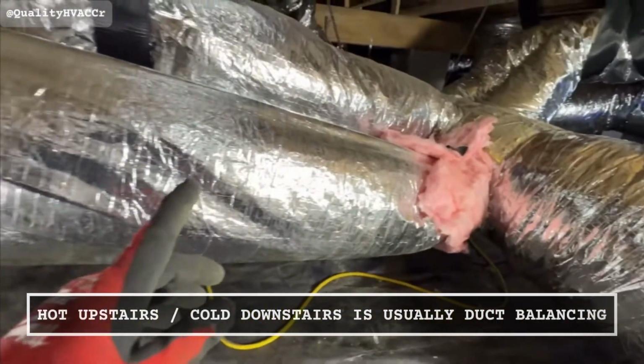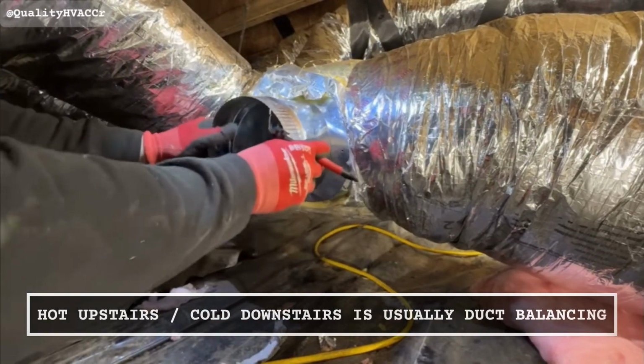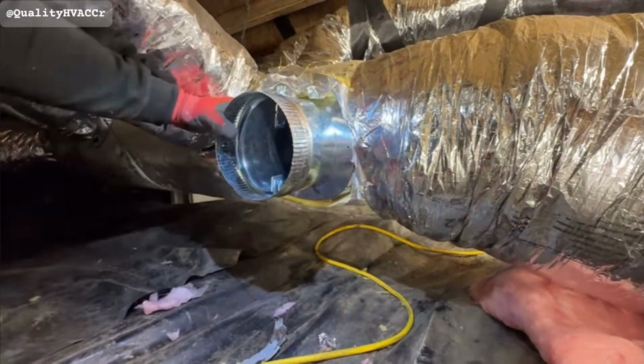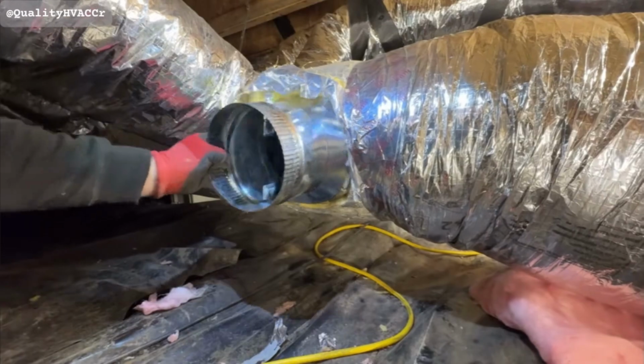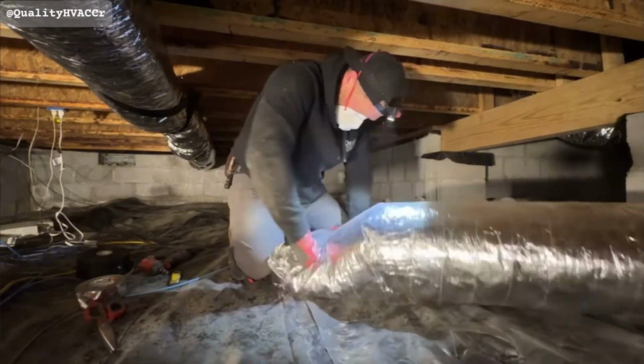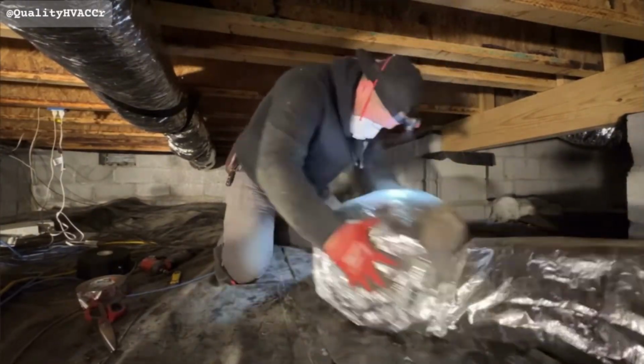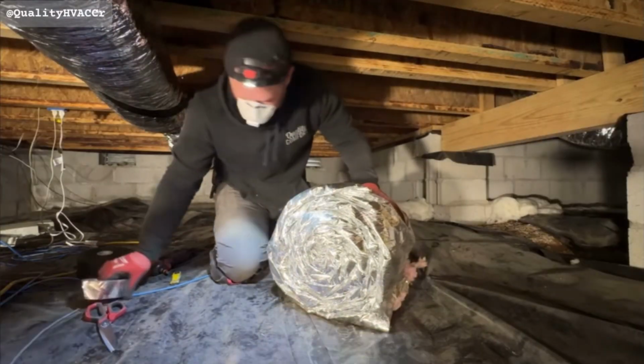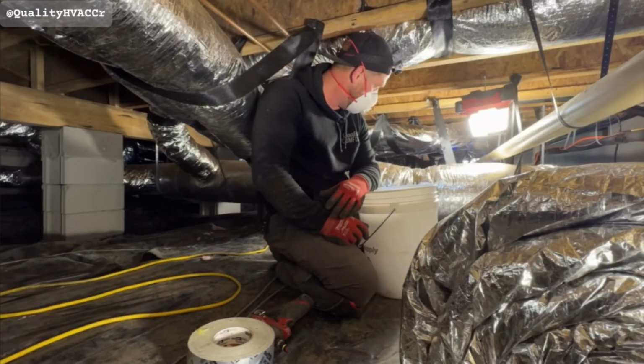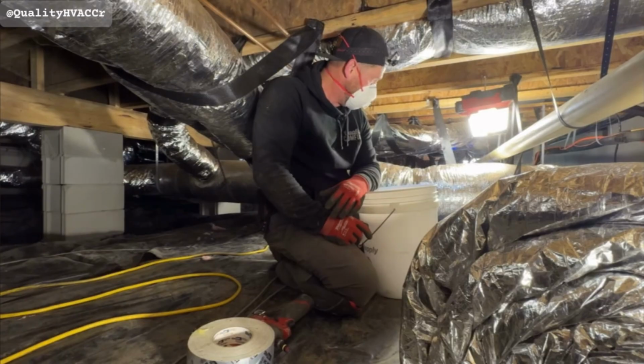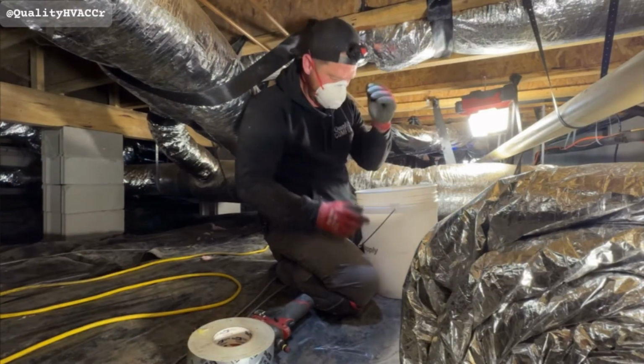Number 6. Indoor air temperature stratification. The hot upstairs and cold downstairs problem is usually a duct balancing issue, not a missing zoning system. Most contractors sell $5,000 zoning to fix what $25 in trunk line dampers will fix. Inline manual dampers installed in the main supply trunks let you balance airflow between floors at the source instead of at each register.